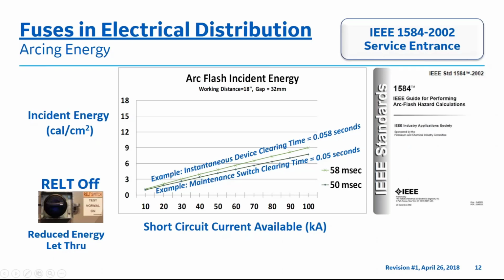How to read this chart. When there is an arcing event at approximately 42 kA, which is labeled with an orange arrow, and using the IEEE 1584-2002 arc flash equations, you will follow the bottom of the orange arrow from the x-axis up to the diagonal line, which represents the clearing time of the electronic device, and you follow it horizontally over to the left, which represents the y-axis, to estimate the incident energy level of approximately 4.5 calories per centimeter squared.